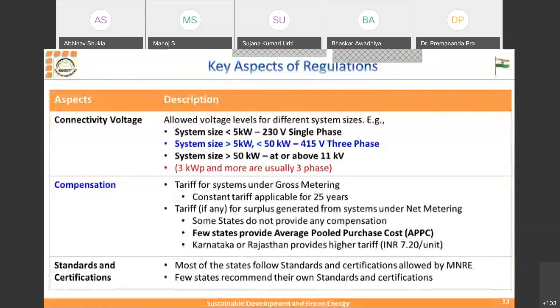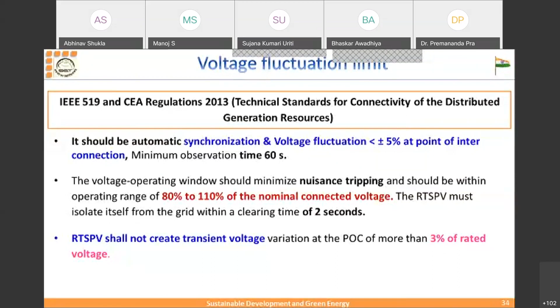IEEE 519 and CEA Regulation 2013 state that synchronization voltage fluctuation should not go beyond plus minus 5%, and minimum observation time is 60 seconds, with 80 to 110% of nominal connected voltage. RTSPV shall not create transient voltage variation at the point of connection of more than 3% rated voltage. So these are some guidelines and regulations for voltage fluctuation.